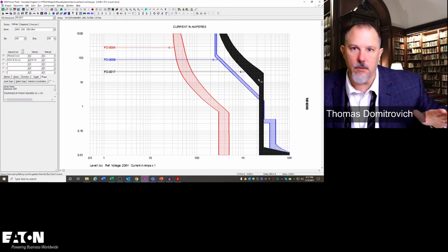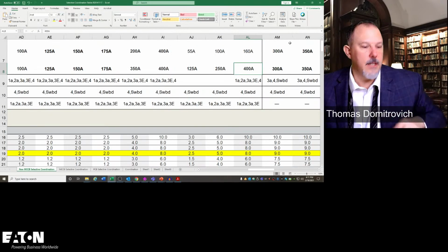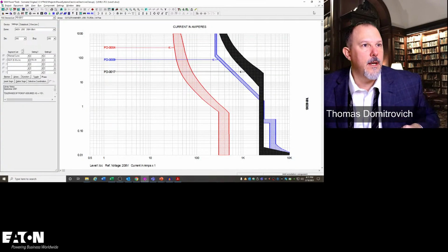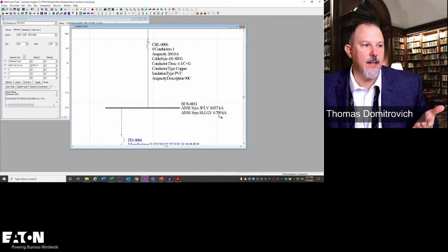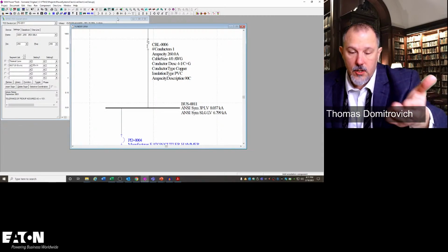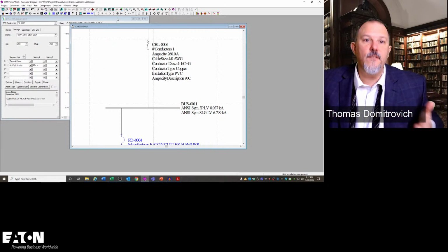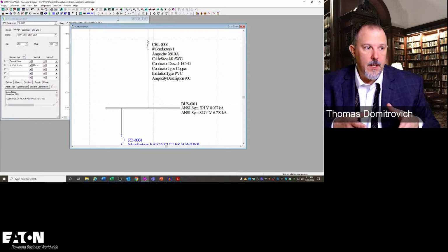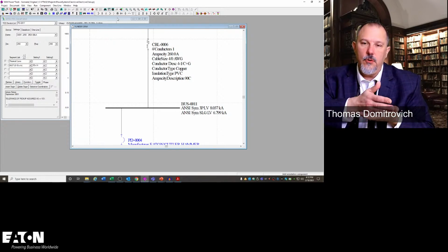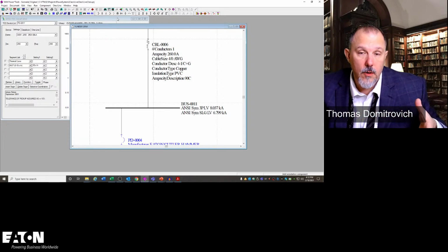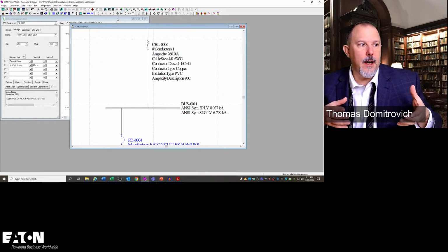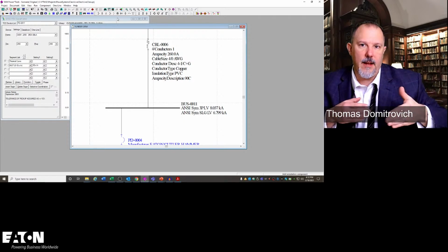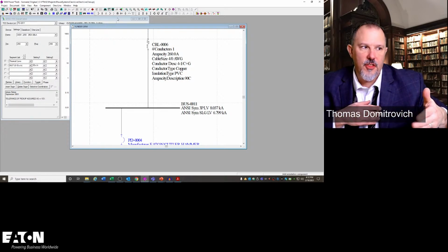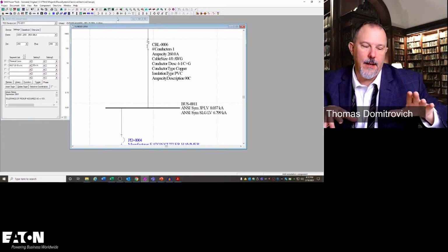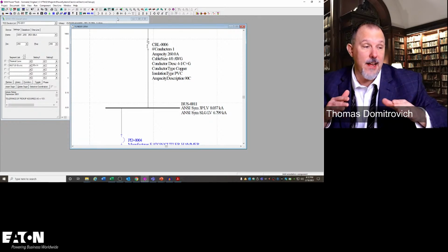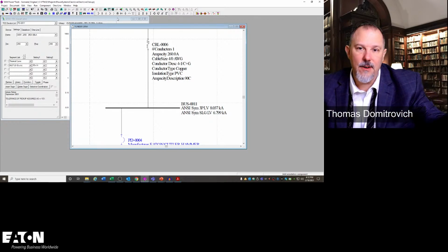8,000, that's going to trip on a ground fault current. What's the ground fault current? Let's look back at SKM, and the ground fault current is 6,799 amps. MC had a question earlier today: what about ground fault currents, do I have to coordinate those? Remember, ground fault currents are a zero sequence current. Yes, we use zero sequence CTs and things like that, but they're real currents, and they can trip a circuit breaker. So I have to coordinate my ground fault curves with my overcurrent curves, and that's a challenge. It really is a challenge. But in this case, my ground fault current is 6,799.